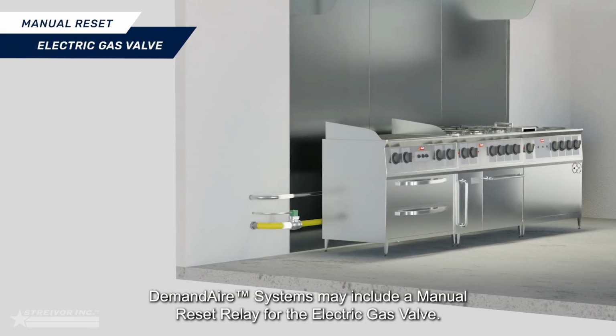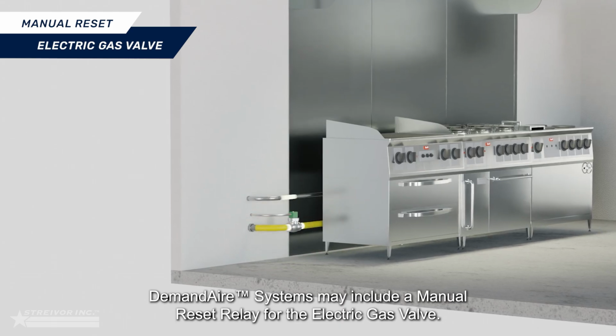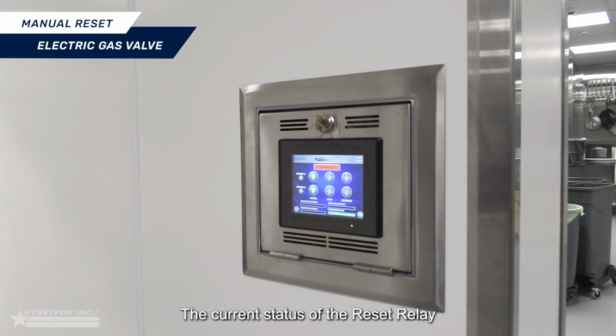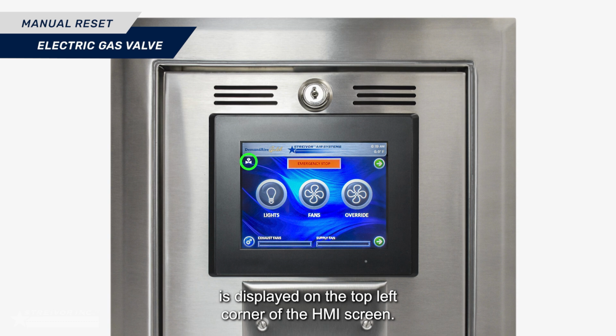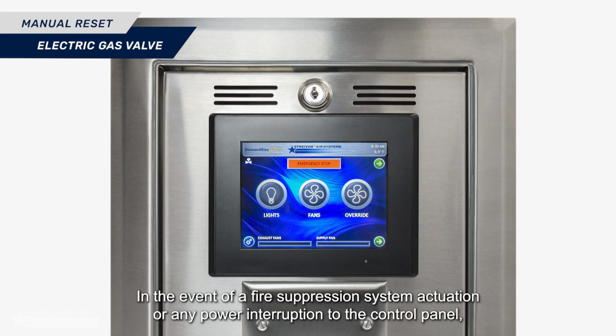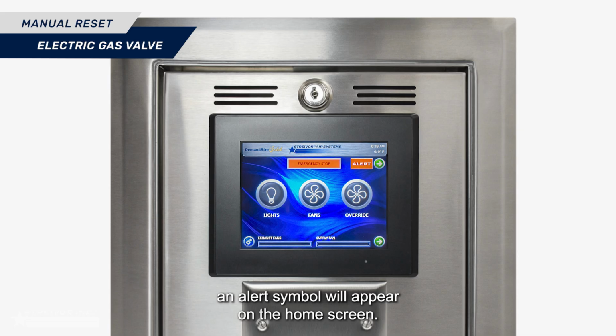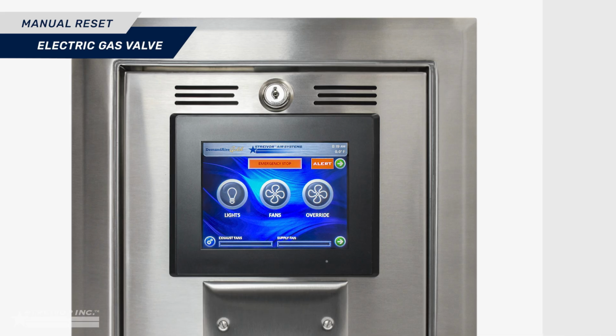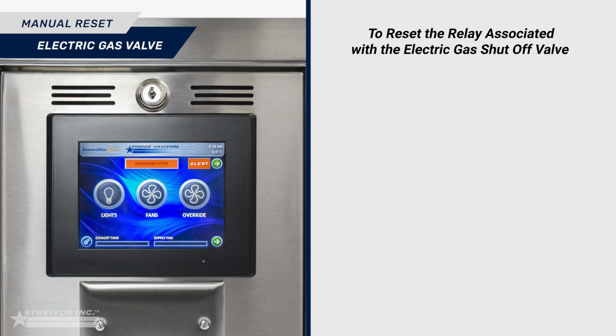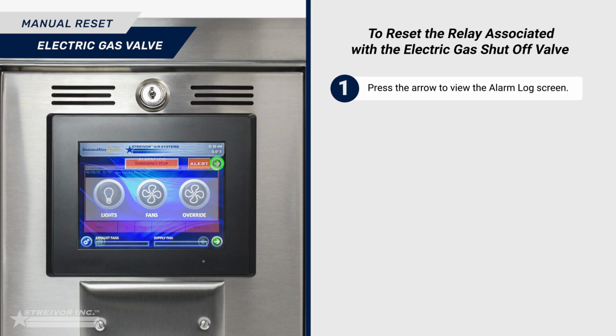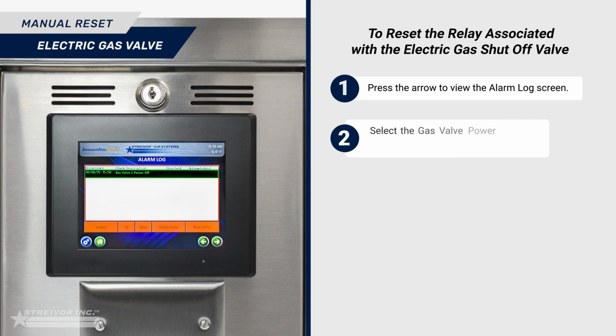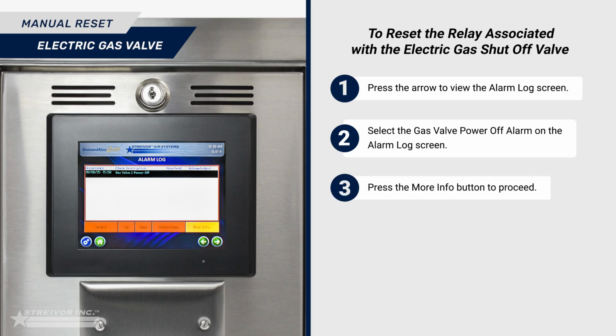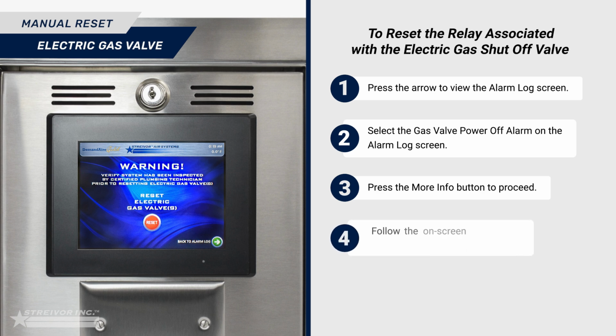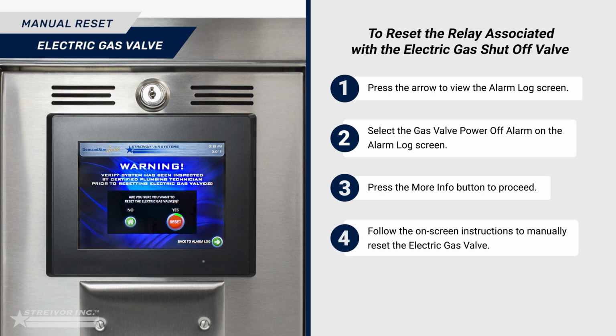DemandAire systems may include a manual reset relay for the electric gas valve. The current status of the reset relay is displayed on the top left corner of the HMI screen. In the event of a fire suppression system actuation or any power interruption to the control panel, an alert symbol will appear on the home screen. To reset the relay associated with the electric gas shutoff valve, press the arrow to view the alarm log screen. Select the gas valve power off alarm on the alarm log screen. Press the More Info button to proceed. Follow the on-screen instructions to manually reset the electric gas valve.